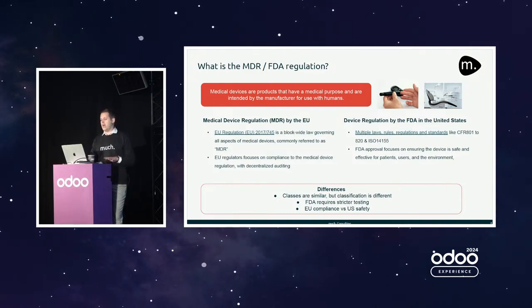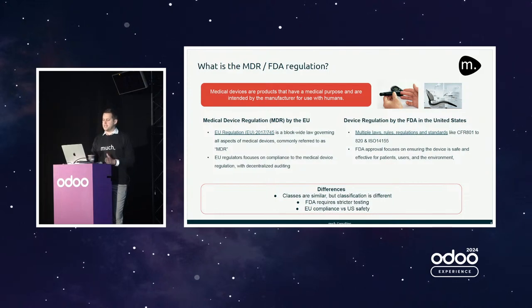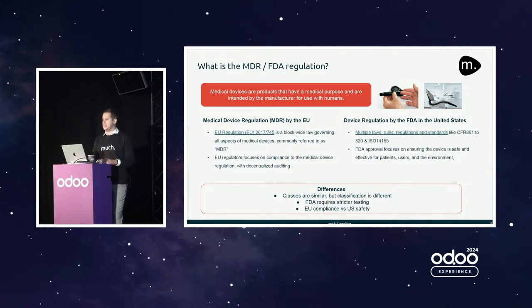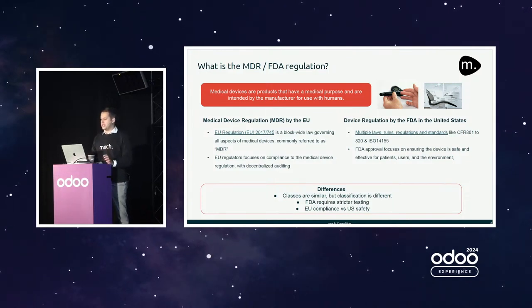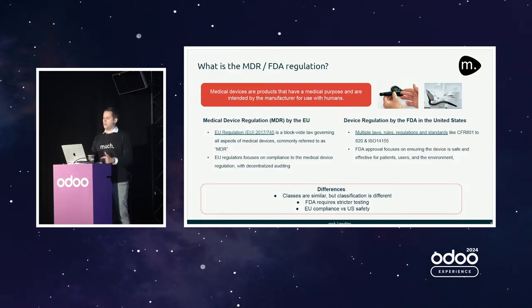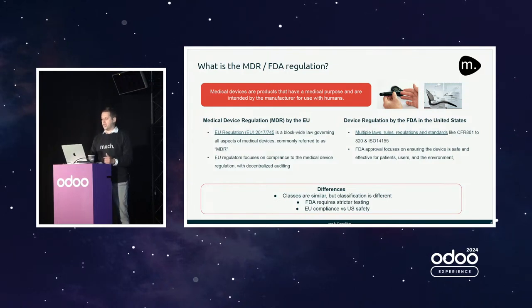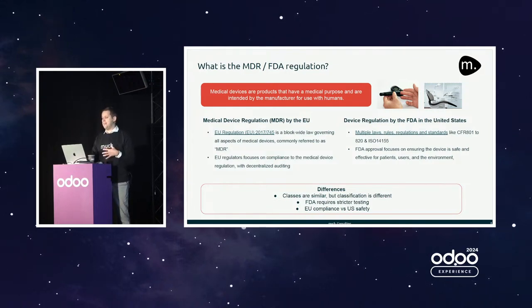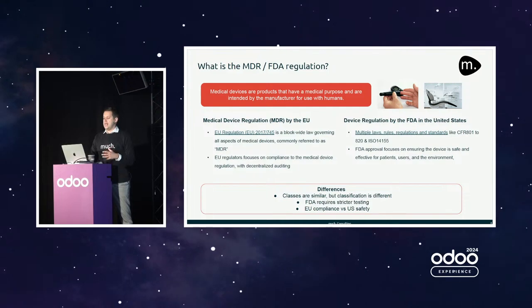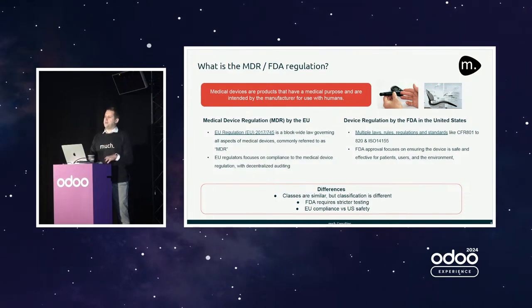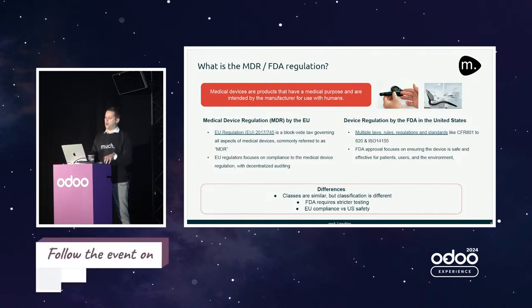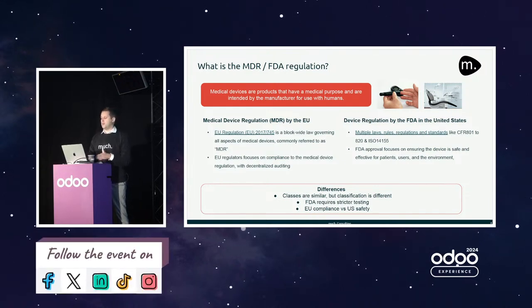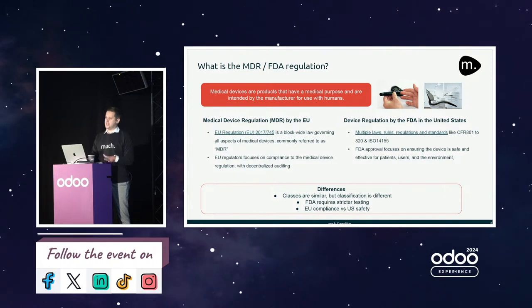In the EU we have a regulation specifically for medical devices. In the US there's a lot of different laws and regulations that play together a little bit. And it's a lot more based on the ISO certifications, as you probably already know. And in Europe, the regulators focus a lot more on compliance, so on actually following the rules, while in the US, what we see often is the focus is a lot more on safety.